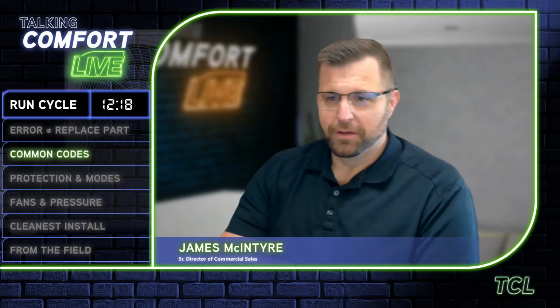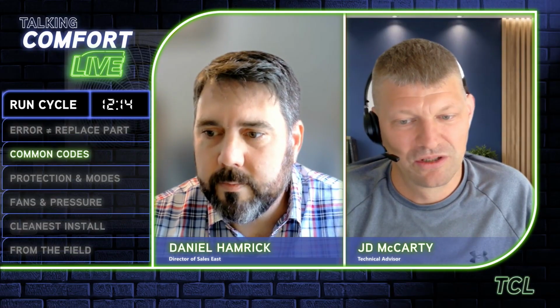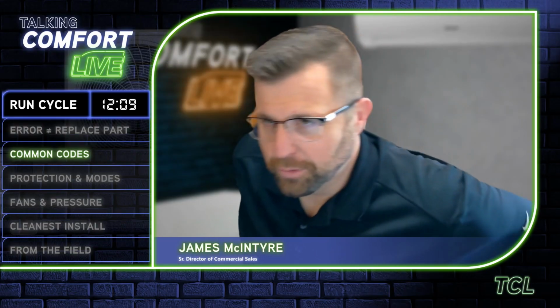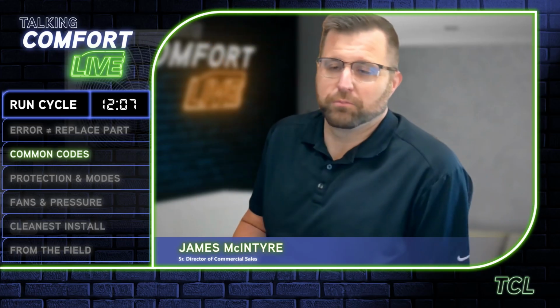If you've got multiple indoor units and they all say communication error, it's probably not going to be one of your indoor units. Just process of elimination. I know I'm not a scientist or anything, but also, where to find that information? You're going to have to look at your manual, or use our app, that kind of thing. You go find that information.